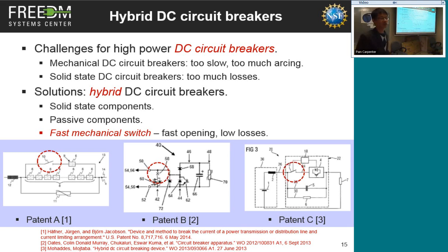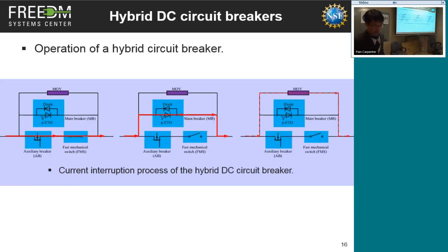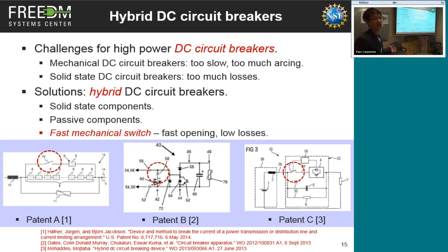So people come up with hybrid DC circuit breakers, in which they will use perhaps a solid state component, perhaps a passive component, and they will also use a mechanical switch. This mechanical switch is used for fast opening during the interruption process, and it is used to reduce the conduction loss during normal operation. There have been a few different patents in the last 5 years. The topology may be different. You may have options for which topology you want to go with, but really you only have one option for the mechanical switch, and that is a fast mechanical switch. So that is why this topic is about this fast mechanical switch.